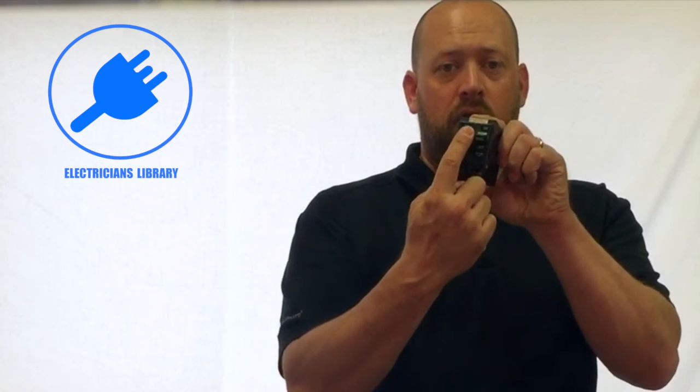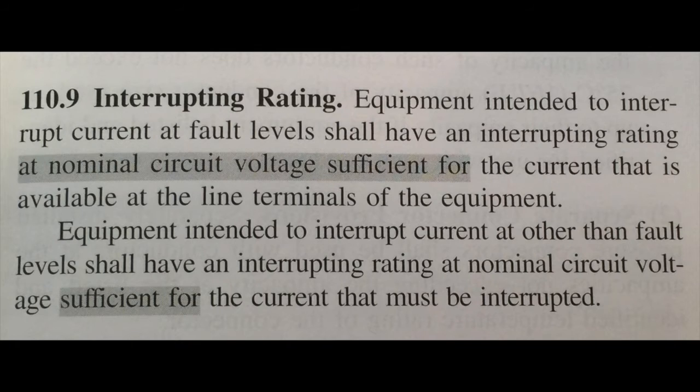In article 110.9 of the NEC, it states, equipment intended to interrupt current at fault levels shall have an interrupting rating at nominal circuit voltage sufficient for the current that is available at the line terminals of the equipment.